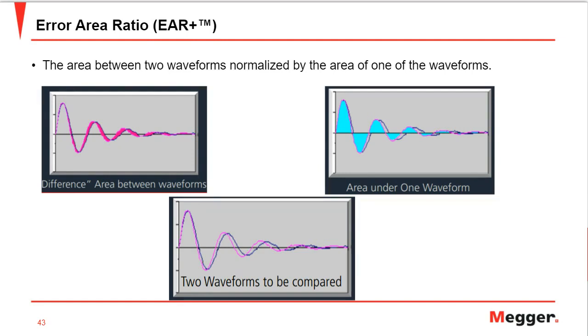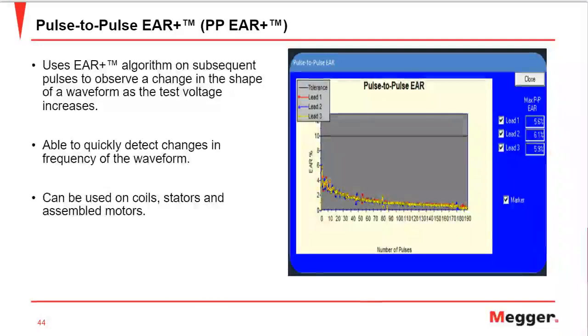Also, in surge testing, there are two types which we can call. One is the pulse to pulse EAR, and the other one is line to line EAR. The concept and methodology are the same, there's just a difference of a few factors, and we'll see the pulse to pulse EAR test first. Pulse to pulse EAR of course uses the EAR plus algorithm on the subsequent pulses, the pulse which was sent next, and then the pulse after that, just to observe the change in the shape of the waveform as we increase the test voltage.